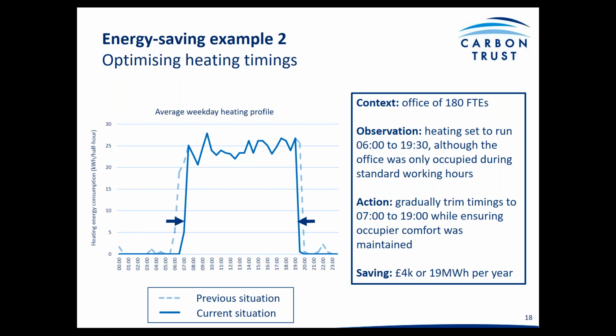The dashed line on the graph shows the week before adjustment, frequently starting very early in the morning and overrunning in the afternoon. The bold blue line shows the system after adjustment, adapting more effectively to the weather by switching on later than the standard timing schedules required and switching off earlier in the day. Both weeks had similar weather and occupancy, and activity levels were fairly consistent. This saved approximately £51 a week from gas, as well as additional energy savings from reducing the runtime on their HVAC system.